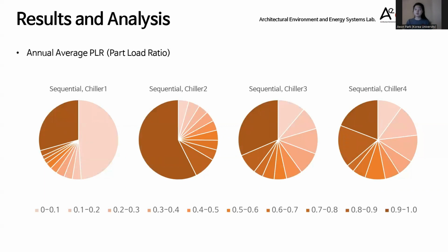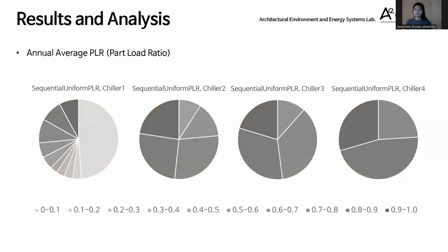The annual part load ratio for each of the four chillers when operating with the sequential algorithm is shown. Similarly, darker colors indicate higher part load values. In the sequential algorithm, it can be noted that there is significantly less operating time at lower part load for chillers 2, 3, and 4 compared to the uniform algorithm. The following graph represents the annual part load ratio for each of the four chillers when operating with the sequential uniform parallel algorithm. It can be observed that this algorithm operates with very high PLR for chillers 2, 3, and 4, unlike the other algorithms.